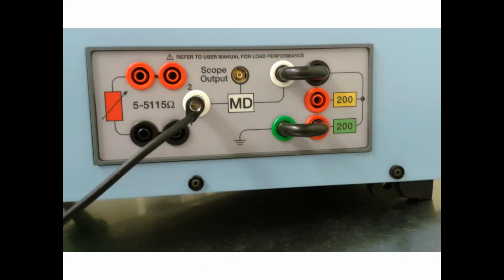So here are the connections that we would make on the side of the generator. This shows one of the tines from the generator coming into the Unitherm, going through our current transformer, and then a couple of jumpers connecting the 200 ohm resistor down to earth ground. Notice that there's also a scope output right above the measuring device, above the current transformer, so you can always hook an oscilloscope here to monitor the current waveforms being generated if you choose to.